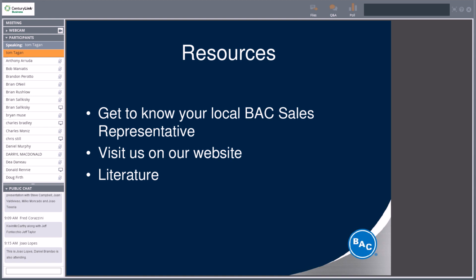Resources. Get to know your local, I'll cover up the BAC, but your local cooling tower sales representative. One of the things that we offer, and I know the competitors offer, is a free cooling tower inspection. So if you're concerned about the general condition of your cooling tower, call your cooling tower rep up, have them come out and take an inspection. Number one, they can run through the tower's operation if you're not familiar with exactly how it works. And number two, they can tell you how many seasons they think you can still get out of it, whether the bearings are starting to go, whether your fan housings are starting to go, whether that shaft looks like it may need replacing.